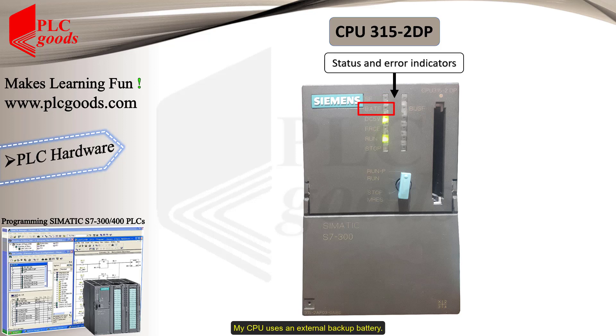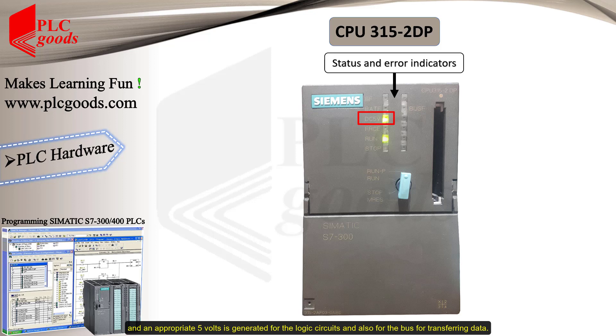My CPU uses an external backup battery. The second LED indicates whether the connected backup battery is OK or not. When the next LED is green, it means the CPU is powered and an appropriate 5 volts is generated for the logic circuits and for the bus for transferring data. When the FORCE LED is a steady yellow, it indicates that at least one of the PLC inputs or outputs is forced to ON or OFF.